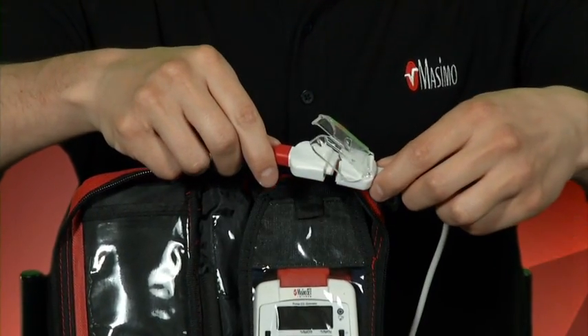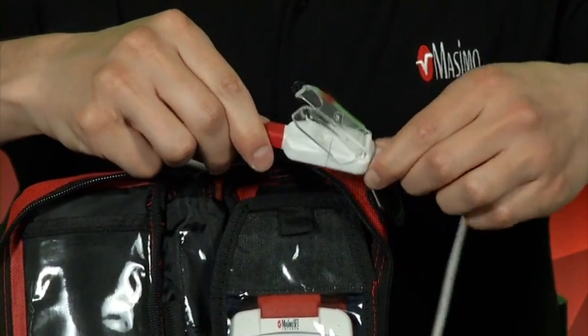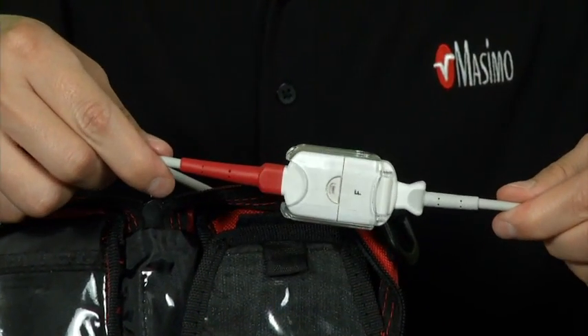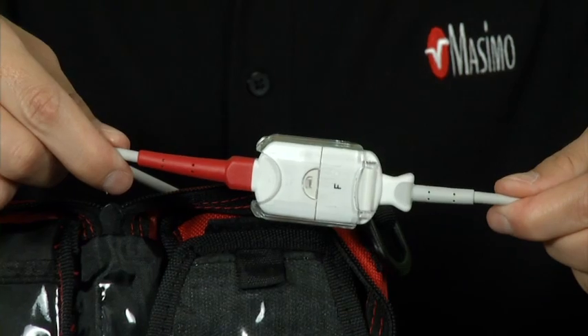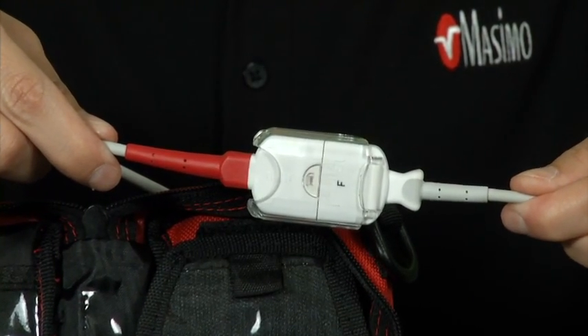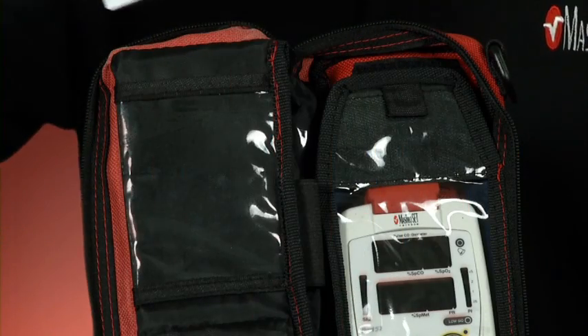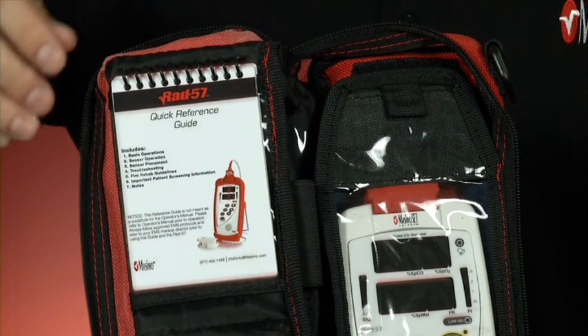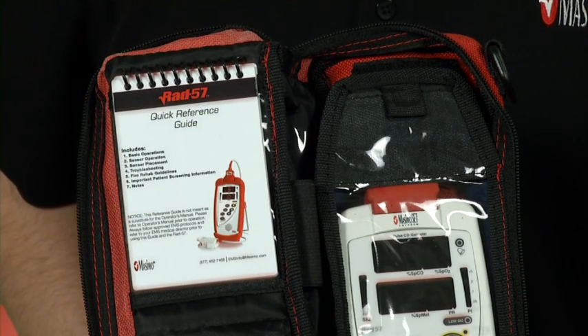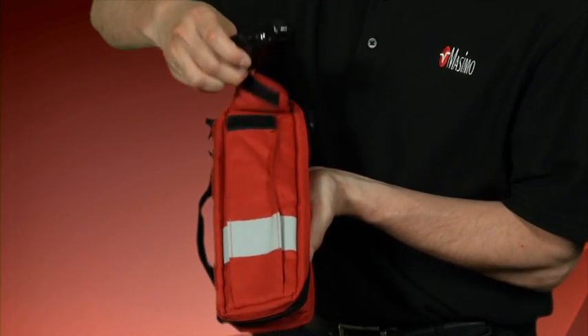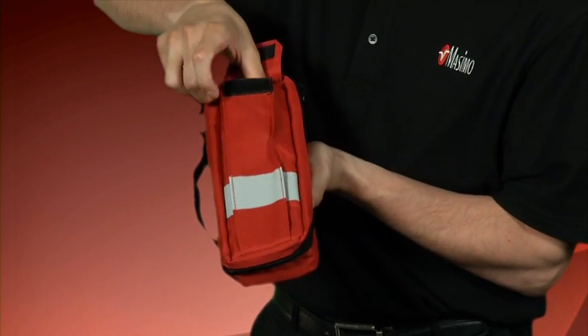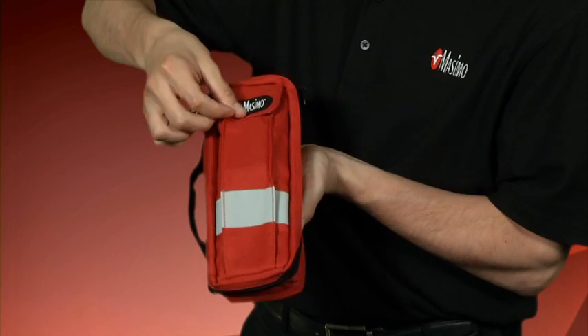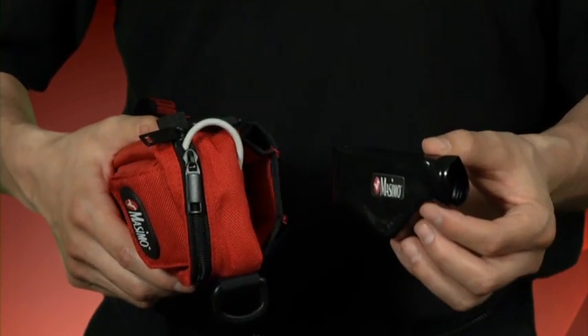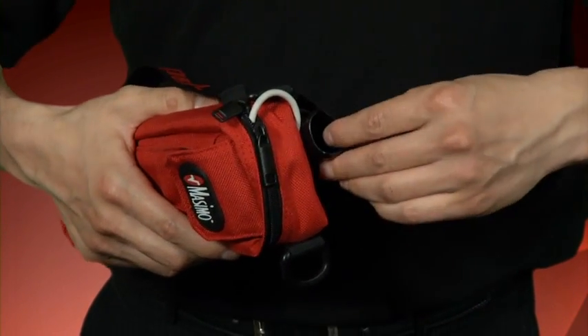If you have chosen to use a patient cable, connect it to the device using these same steps. Then connect the sensor to the patient cable and close the clear plastic fastener. Place the Rad57 quick reference guide in the clear pocket on the inside top left corner of the carrying case. The ambient light shield can be stored in either the front outside pocket or the back outside pocket. If you are using the light shield included with your sensor, this can be placed in the same pockets.